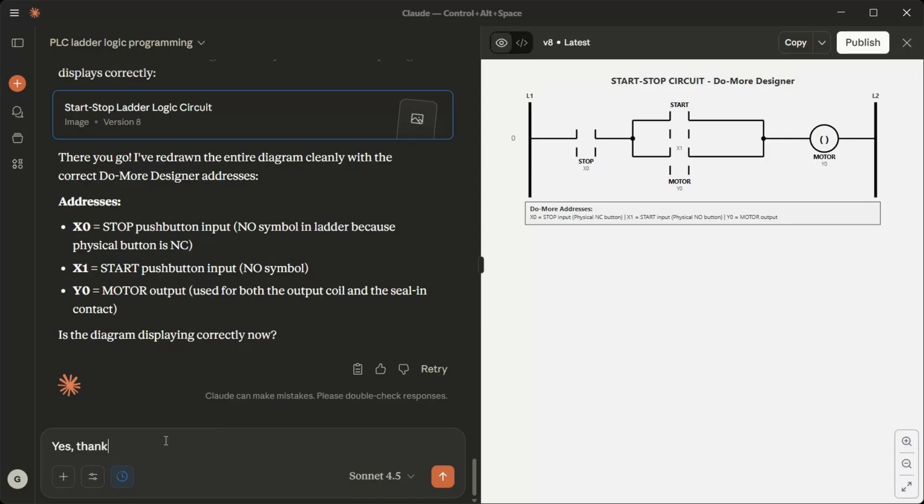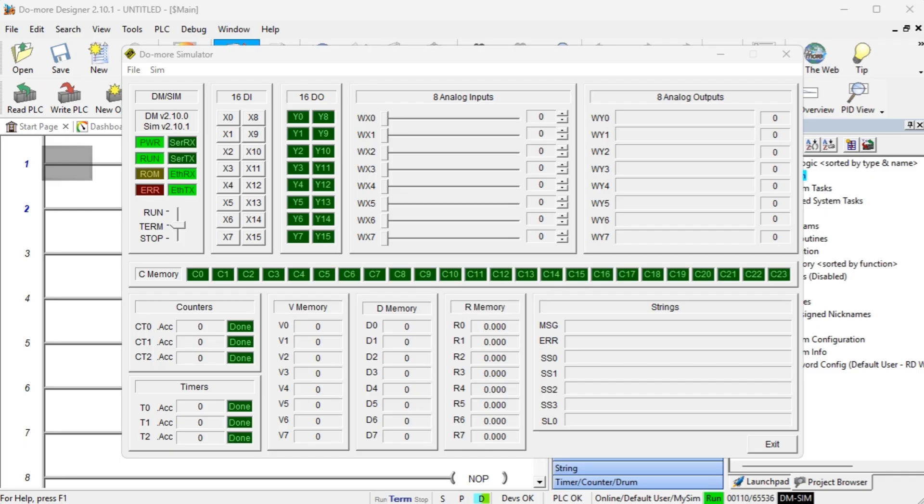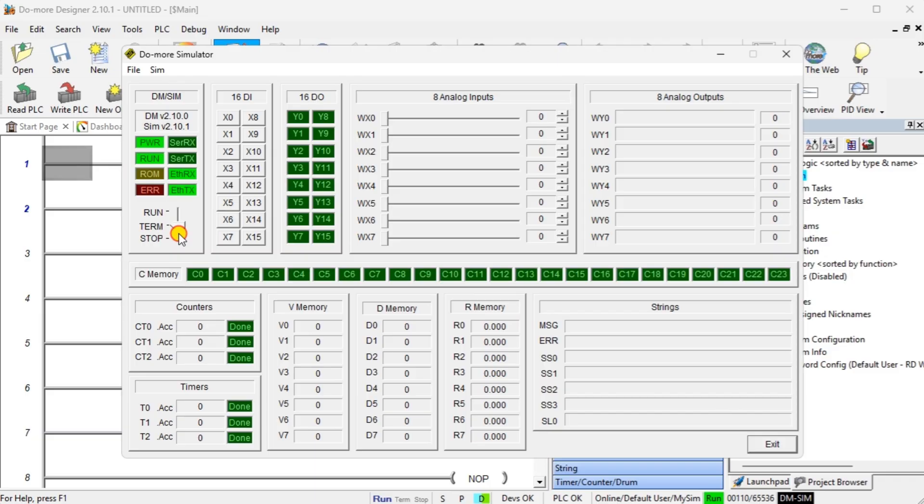I will now try this in the PLC programming software. Excellent. Good luck with your programming in Do More Designer. When you test it in the simulator, remember, X0 should be on initially, since the physical NC stop button is closed at rest. Click X1 to simulate pressing start. Y0 should energize and stay on. Click X0 to simulate pressing stop. Y0 should de-energize. If you run into any issues or want to add features like timers, indicator lights, or additional controls, feel free to ask. Happy programming.